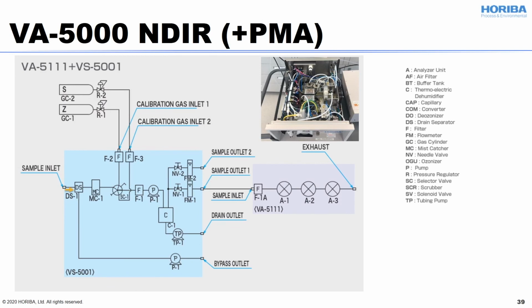First of all, the drain separator will drop the moisture out, and the mist catcher will catch the SO3, and you don't want to carry SO3 forward because it damages the analyzer. And here is a line selector for the sample line or cal line. Alright, this is the filter, replaceable, and the pump inside. And here is the sampling cooler unit, saturated at 5 degrees C to drop the moisture. And these are the needle valves to adjust the flow.